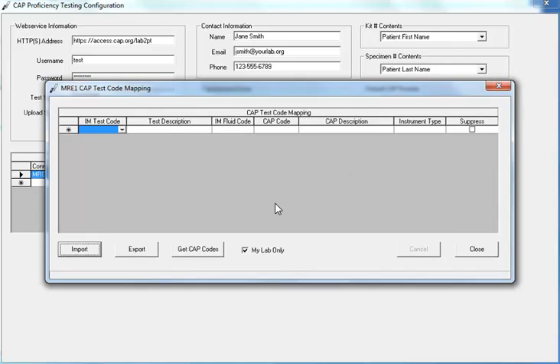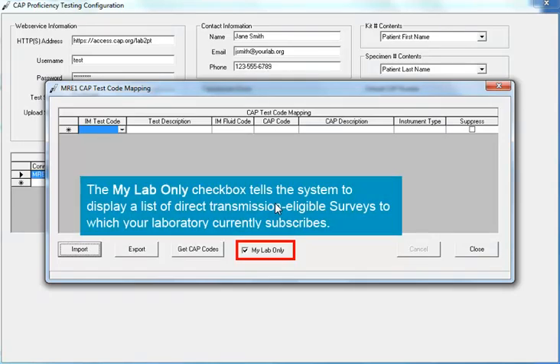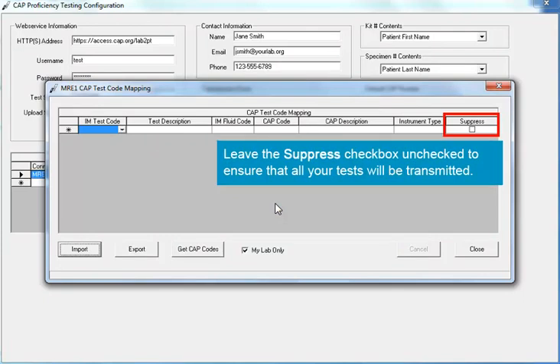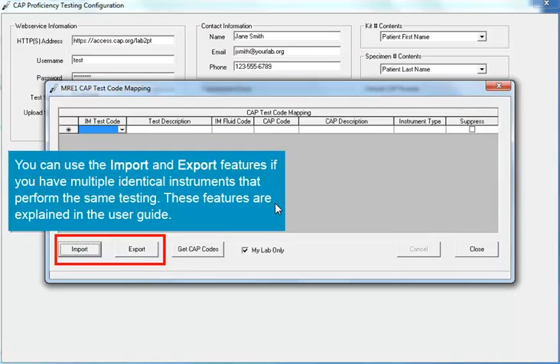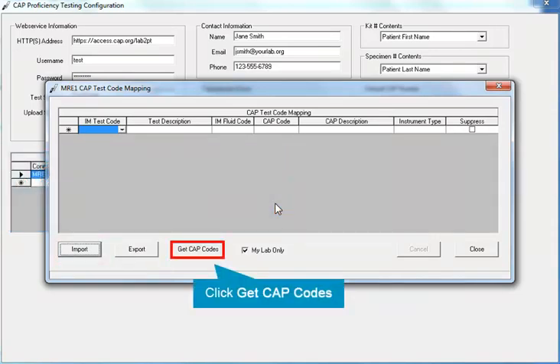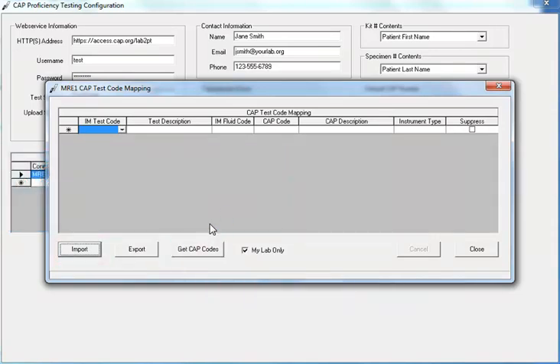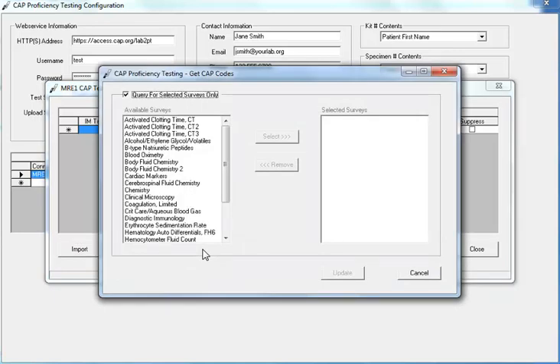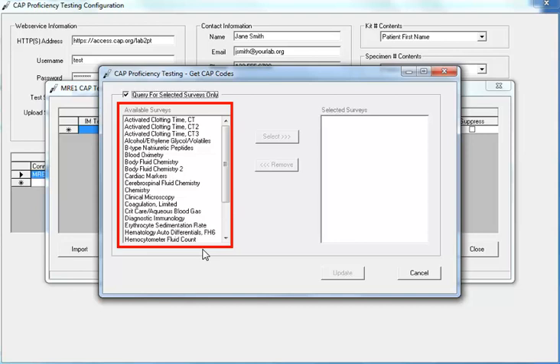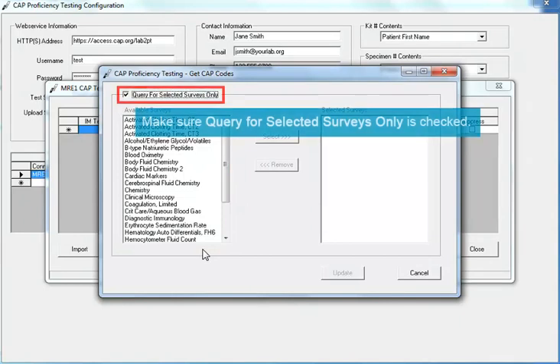On the CAP Test Code mapping screen, verify that the My Lab Only checkbox is checked. This tells the system to display a list of direct transmission eligible surveys to which your laboratory currently subscribes. Leave the Suppress checkbox unchecked to ensure that all your tests will be transmitted. You can use the Import and Export features if you have multiple identical instruments that perform the same testing — these features are explained in the User Guide. Next, click the Get CAP Codes button. The Get CAP Codes screen appears, displaying only the direct transmission eligible surveys that your laboratory has ordered. Make sure the checkbox for Query for Selected Surveys Only is checked.